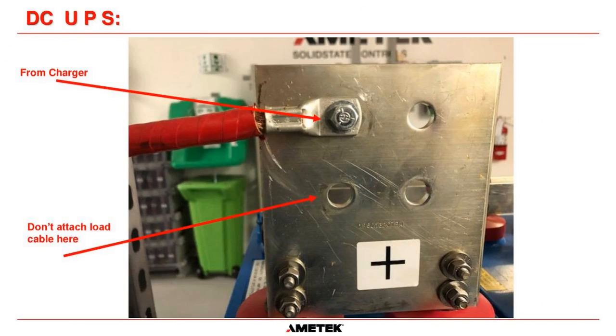What you can see is on many lead acid systems, you will see a big bus plate, this big bus plate here that is connected to the main positive using these bolts here. Okay, and then what the plant does is they'll connect the cable from their charger to the battery at this point here, and then they'll connect their load cable to this point here and take that out to the load.